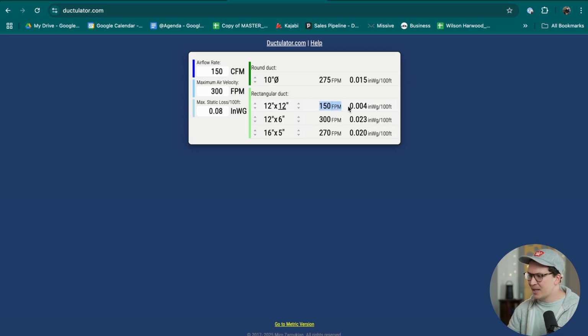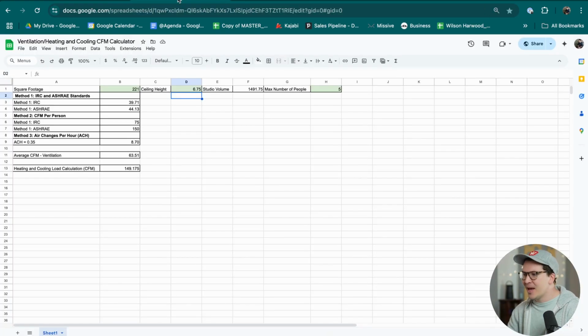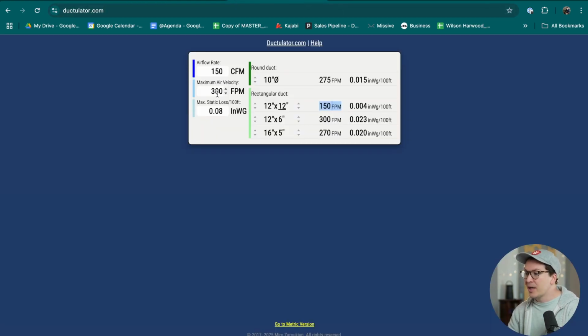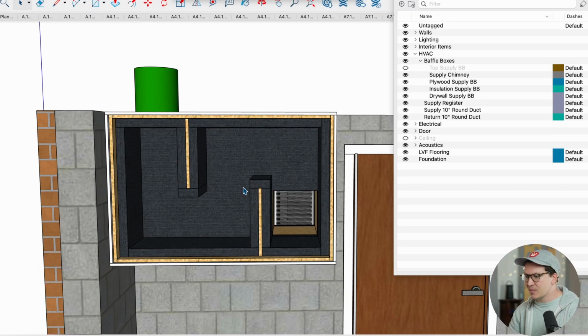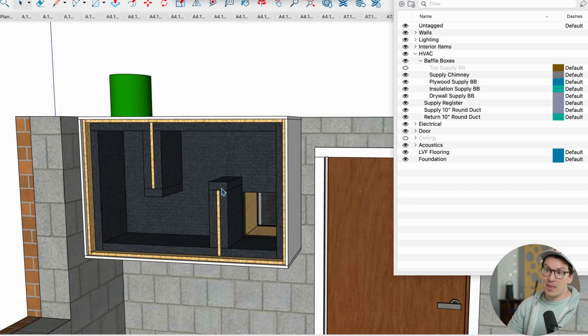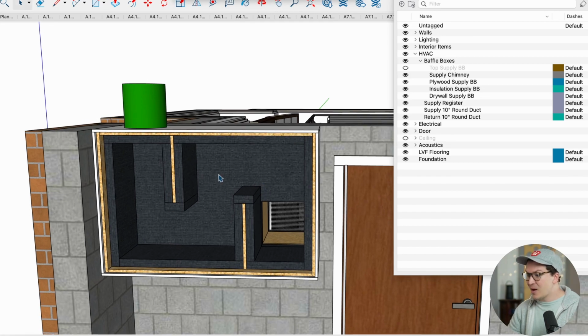We get a nice solid 150 feet per minute. We are half the speed of the maximum air velocity, and everyone's happy. That air is going to slowly just drip into the room and you won't hear it at all. It is a beautiful thing, everybody. Beautiful, beautiful. And so what we want to do here is make sure we over-design our baffle boxes when possible. So the bigger you can make these things, the better, as you can see. So that's how I designed it.